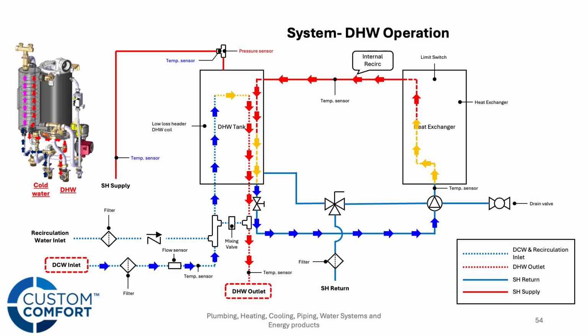And I say that because you can have some simultaneous domestic output as well as heating output with this. It's not a flat plate. We're not diverting water to the flat plate versus the rest of the heating system. On this, you could pull off both domestic and heat all at the same time. The one thing to know is your heating is limited by the domestic output, right? You're going to rob heat out of that buffer tank to heat the domestic hot water. So it's limited in its capability, but it does have that ability.